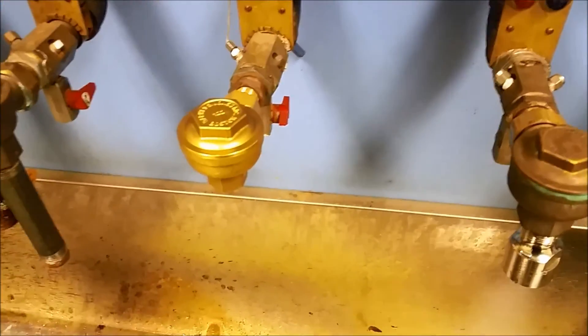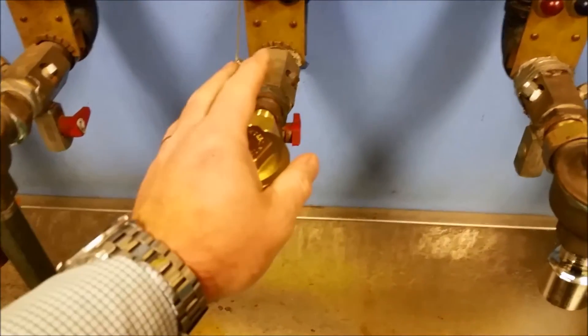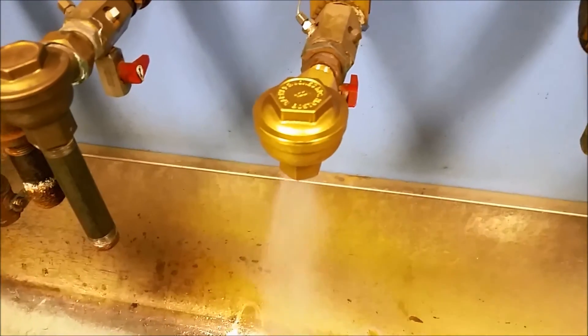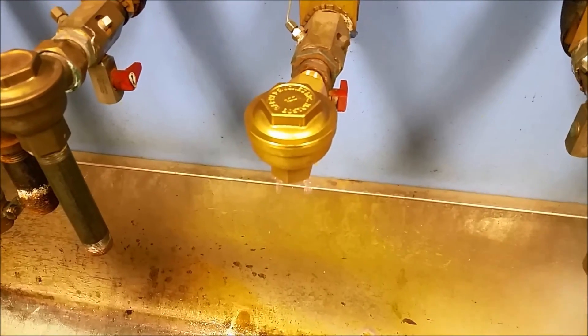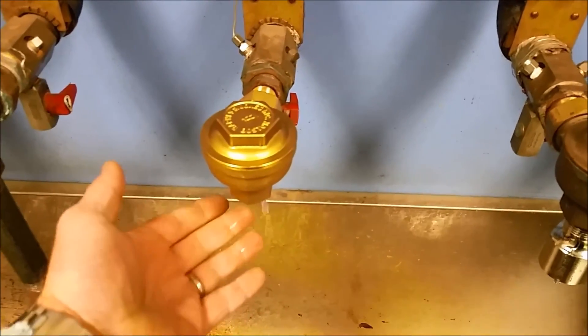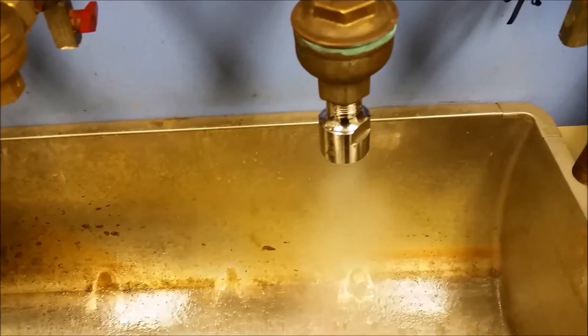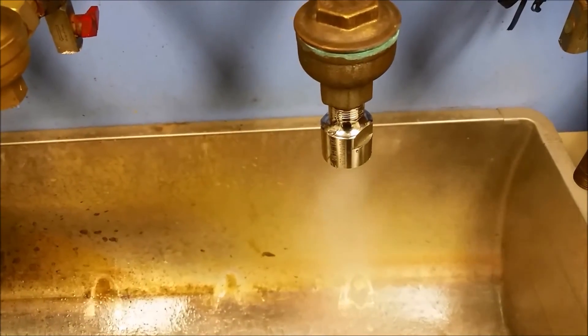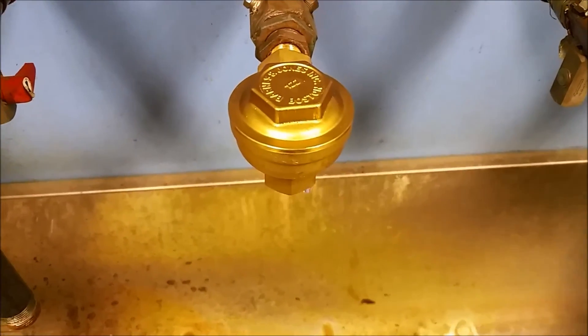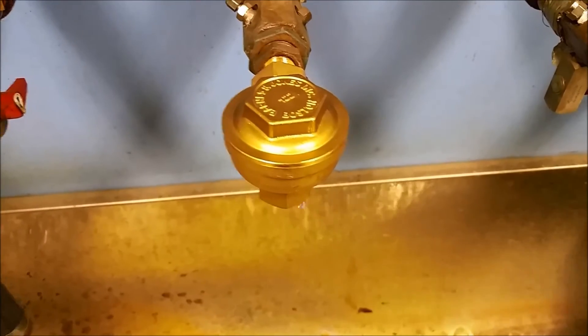Let's compare that to a regular — this is a Barnes & Jones 122 cold start. Dripping condensate like it should, but no steam, versus a fixed orifice trap: dripping condensate like it should, no loss of steam.